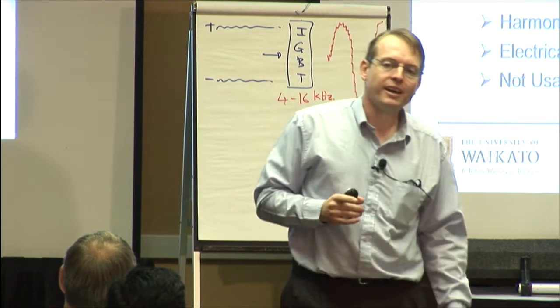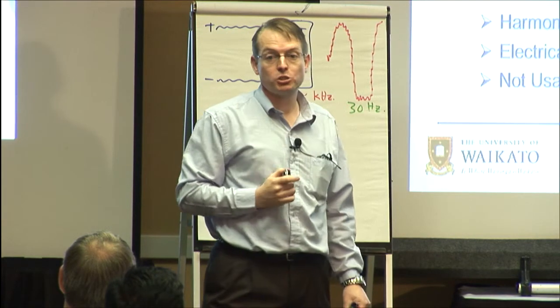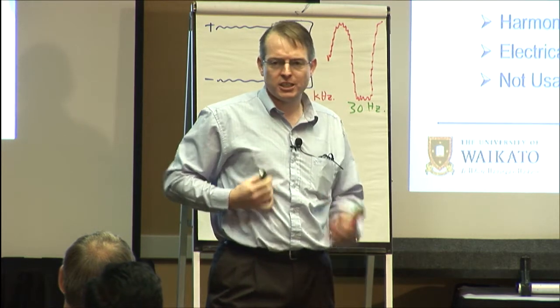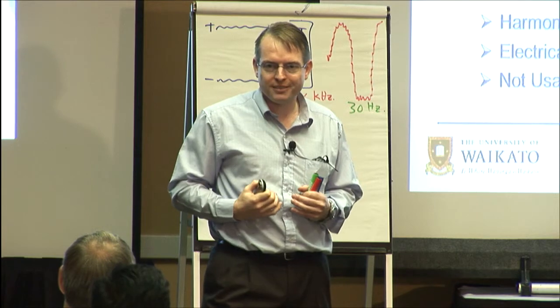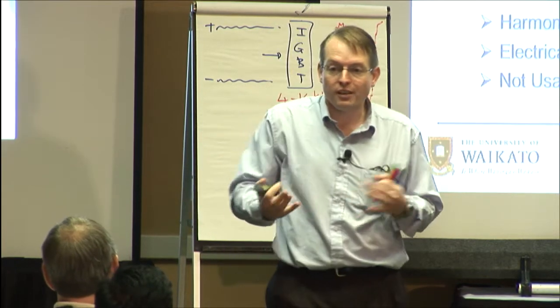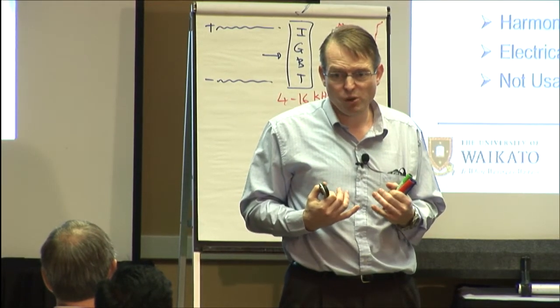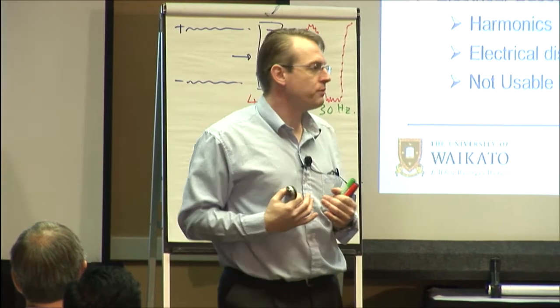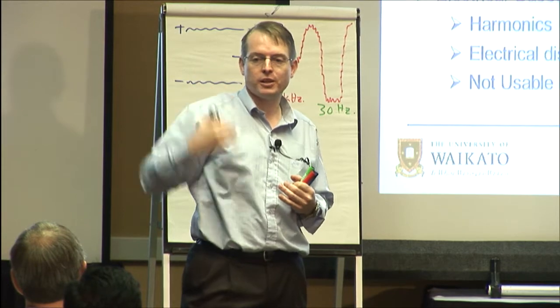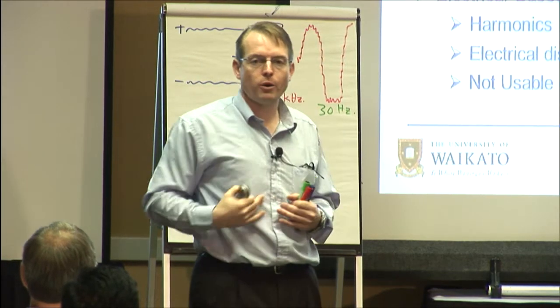What can happen is those harmonics actually propagate back down the distribution lines. Has anyone ever had a problem where you've had really dirty power and your TV sort of starts to lose reception and that sort of thing? Probably much more prevalent in sort of the third world now, as they've mostly gone on top of it with modern switchgear and whatnot, but it used to be a real problem 10, 15 years ago. And that's harmonics propagating back up the transmission line, in the same way that harmonics go downstream to your motor as well.